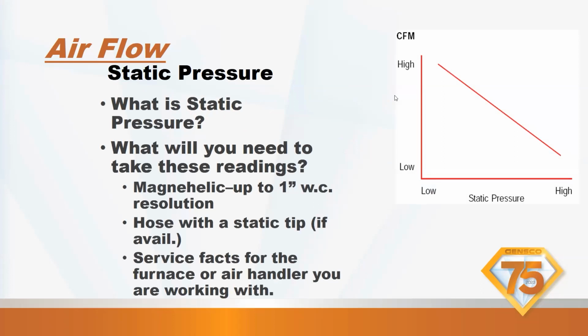Static pressure. Static pressure is the balloon pressure inside the duct. Okay. So what we're going to do is we're going to measure the total static pressure by taking readings at the inlet of the furnace or the air handler at the return. And then we're going to take a reading at the supply of the furnace before the coil or the air handler right at the outlet of the air handler. The reason we have to take it before the coil on a gas furnace is we can have multiple different coils, even different brand coils attached to our gas furnaces, okay? That's why they cannot tell us what it is on the outlet of the coil.